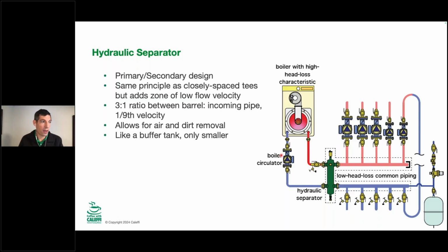If you make that, you can absolutely make this less expensive if that's a 1.25 inch barrel from the top to the bottom. You may have broken that rule of primary secondary piping, and again, you will absolutely be able to test that if you put in a flow meter right here and see if there is flow induced from left to right when you get to the maximum flow rate that was advertised for that hydro separator. If it says that it can take 40 GPM and you turn on 40 GPM worth of system flow, and then you see past 35 GPM that this has 1, then 2, then 3 GPM of flow rate on the left side here, we just aren't separated anymore.